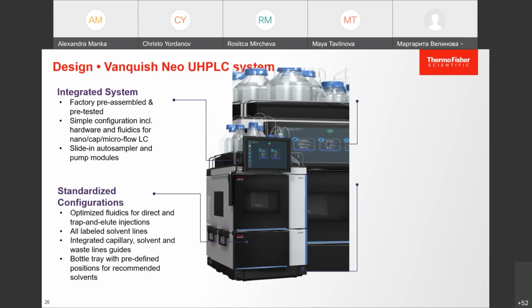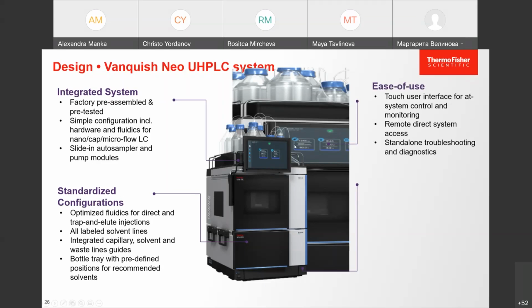So this is how it is designed. You have all labeled solvent lines, integrated capillary, solvent and waste line guides, and a bottle tray with predefined positions for recommended solvents on top of the system. It has then the easy-to-use user interface for system control and monitoring. So you get this display with the system. Like on the Core, it's optional, but here it's included with the system. You can control the system from this user interface, and it helps you with troubleshooting and diagnostics.